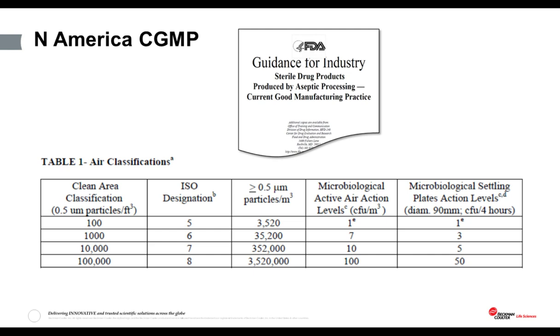Let's take a look at the North American CGMP document. This differs from the European and World Health guidance in that it only mentions one particle size — the 0.5 micron particle. However, any manufacturer based in North America wanting to sell their products outside of North America must count both 0.5 and 5 microns, as they must be in compliance with the standards of the country to which they export their products.